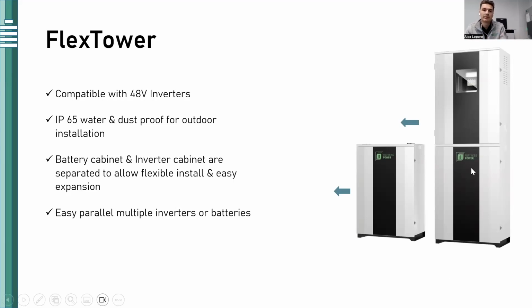On that DIN rail is where you'll have your combiner block for all the batteries sitting in this cabinet. There's also an area where you can put a heater, like a Stego heater, and a temperature sensor. So if you're in Philadelphia and it's 40 degrees, that temperature sensor will notify the heater to turn on to keep the batteries within our recommended temperature range, which is anywhere from 32 to 114 degrees Fahrenheit.